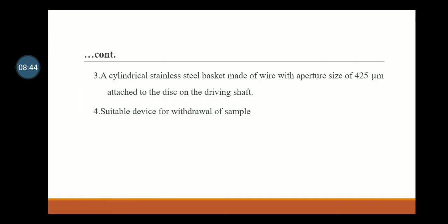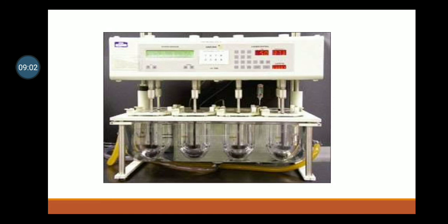Second, an electric motor. Third, a cylindrical stainless steel basket made up of wire with aperture size of 425 micrometer attached to the disc on the driving shaft. Fourth, a suitable device for withdrawal of sample. So this is the diagram or figure of the tablet dissolution apparatus.